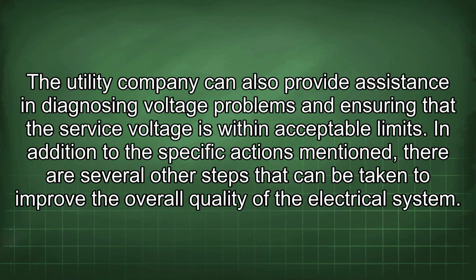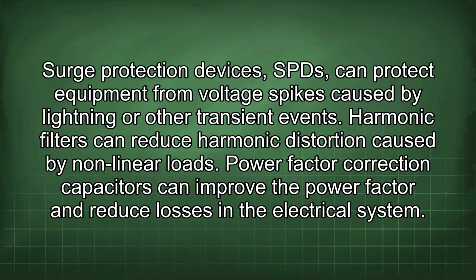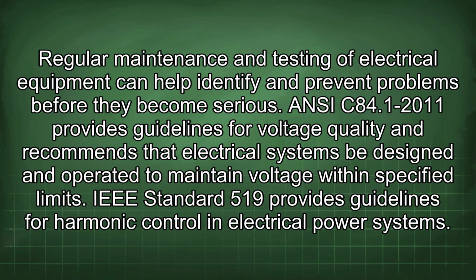In addition to the specific actions mentioned, there are several other steps that can be taken to improve the overall quality of the electrical system. Surge protection devices, SPDs, can protect equipment from voltage spikes caused by lightning or other transient events. Harmonic filters can reduce harmonic distortion caused by nonlinear loads. Power factor correction capacitors can improve the power factor and reduce losses in the electrical system. Regular maintenance and testing of electrical equipment can help identify and prevent problems before they become serious.